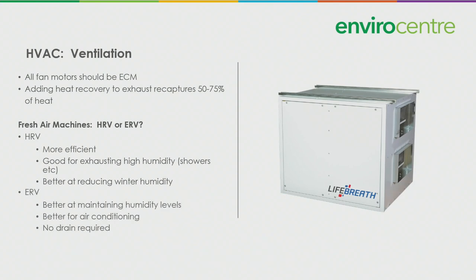If you have an ERV, it's better at maintaining the humidity levels. It's better if you're in an air conditioning situation. You're not going to be bringing a lot of humid air in. It's going to reduce some of the humidity. And there's no drain required from a technical perspective. An HRV has to have a drain to drain off that condensed water. ERVs generally do not need a drain. And the unit in the picture is a commercial HRV unit.